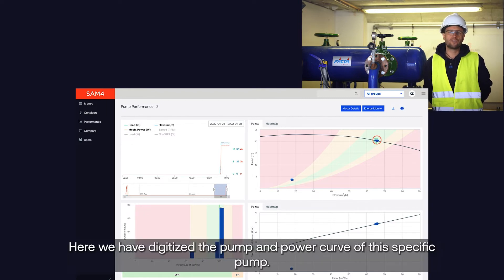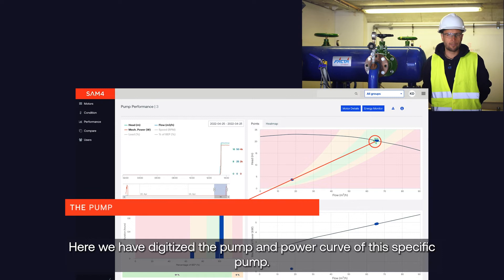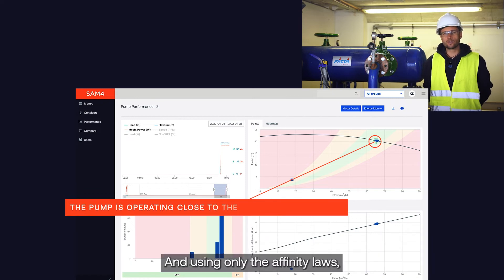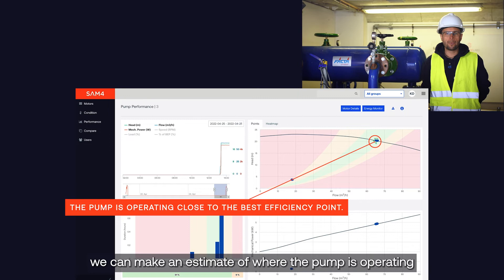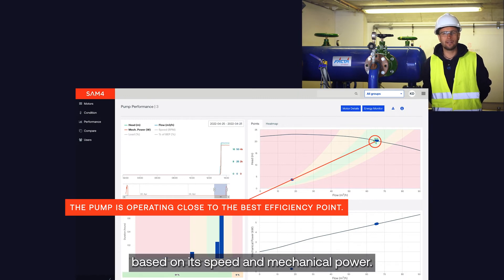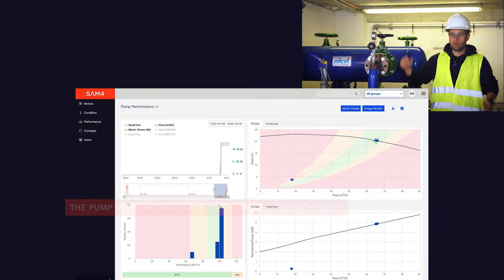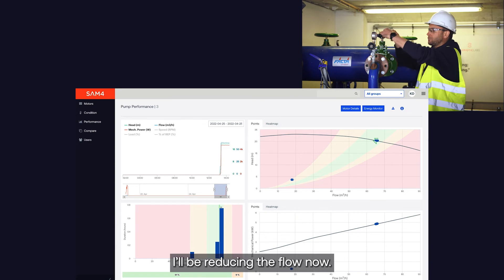Here we have digitized the pump and power curve of this specific pump and using only the affinity laws we can make an estimate of where the pump is operating based on its speed and mechanical power. I will be reducing the flow now.